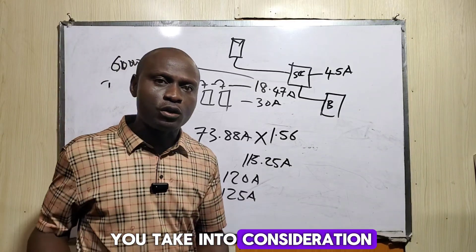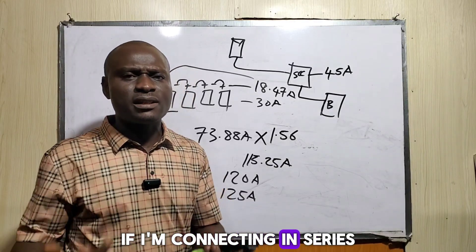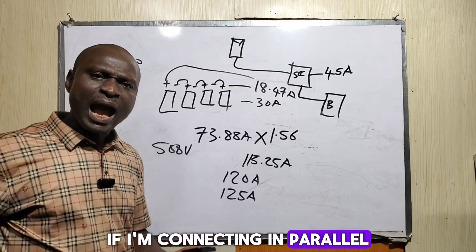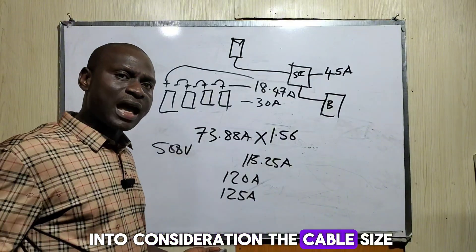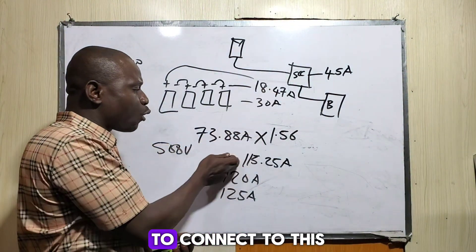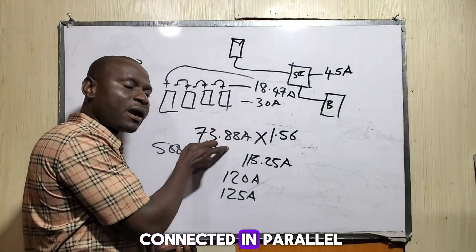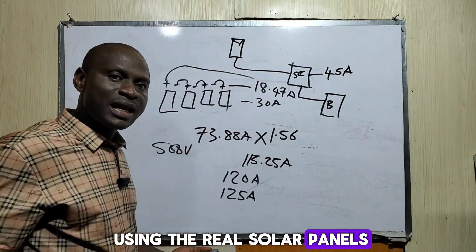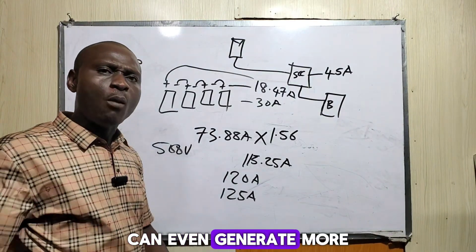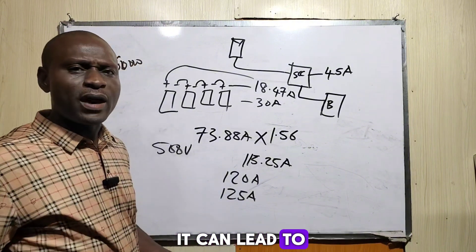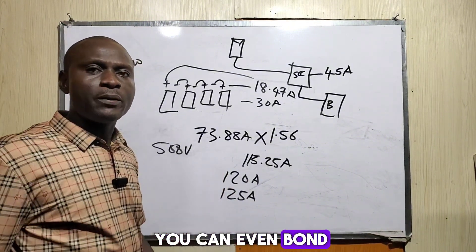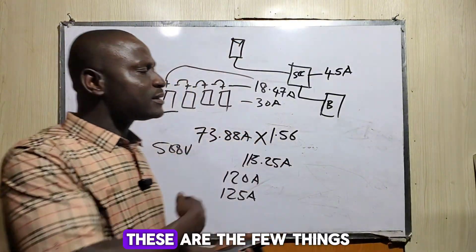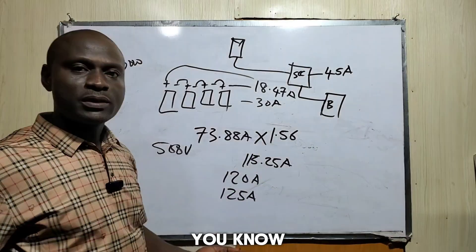If connecting in parallel, you need a much larger cable and a larger breaker. If you use the same cable as for a series connection on a parallel system, the cable will definitely melt and can lead to a fire hazard — the breaker can also trip or burn. These things are very important when sizing a solar power system.